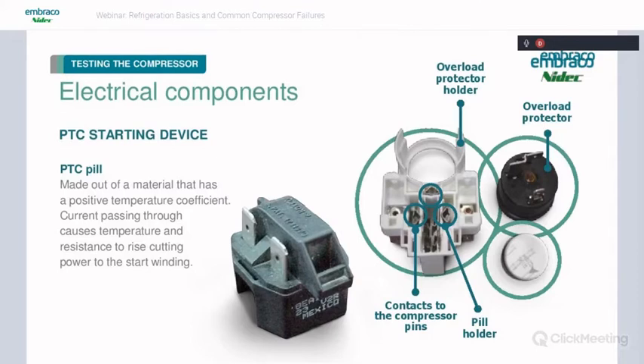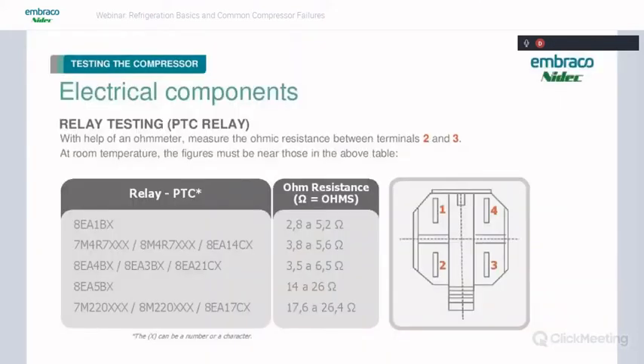Also a very simple device. To test these, you can find a chart like this, which is in Embraco's compressor application manual on their website at embraco.com. Basically, you're going to test the ohmic resistance through terminals 2 and 3, and you can compare it to this chart, or you can just test it and see that you have some resistance. If you don't have any resistance, it could indicate that the pill is broken or damaged. Also, sometimes they'll smell burnt. If you have high current, it'll burn up that pill, and you can tell they're bad that way as well.